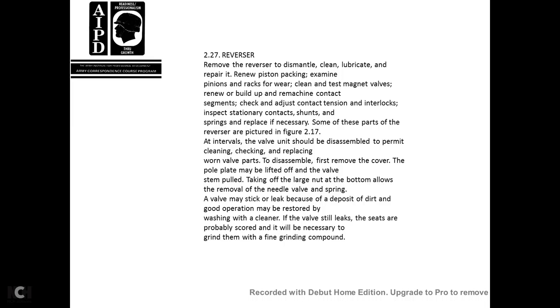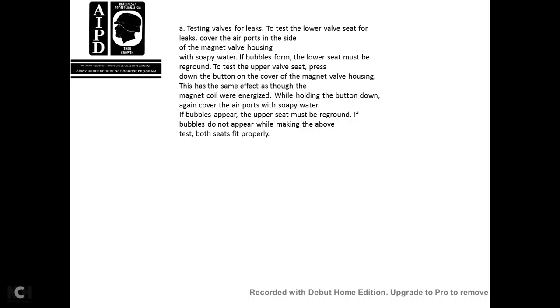At intervals the valve should be dismantled to permit cleaning and checking, replacing worn valve parts. To disassemble, first remove the cover; the power pole plate may be lifted off the valve stem. Taking off the plug at the bottom allows the removal of the needle valve and spring. The valve may stick or leak because of deposits of dirt. Good operation may be restored by washing it with a cleaner. If the valve still leaks, the seats are probably scored and, if necessary, should be ground with a fine grinding compound. Testing valve leaks.